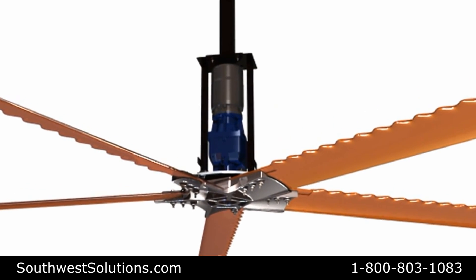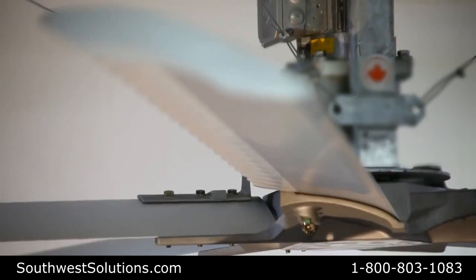We were able to increase the blade pitch, rake, and cut of the blade — from the typical 8-degree pitch used by other high-volume low-speed airfoils to a staggering 21-degree pitch. The tubercle fan produces more air with 5 blades than a competitive airfoil model with 10 blades.